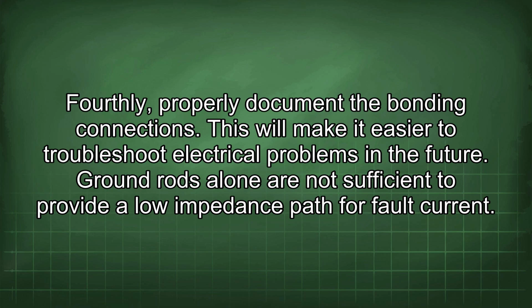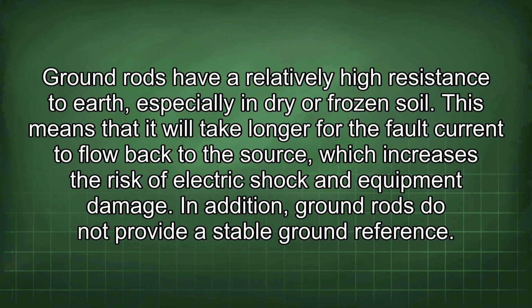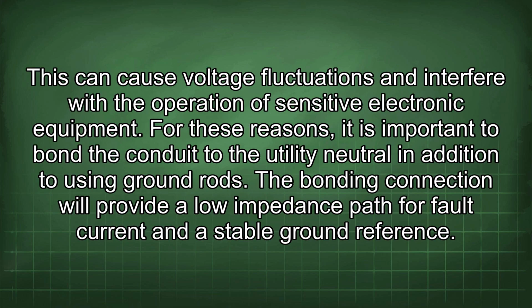Ground rods alone are not sufficient to provide a low impedance path for fault current. Ground rods have a relatively high resistance to earth, especially in dry or frozen soil. This means that it will take longer for the fault current to flow back to the source, which increases the risk of electric shock and equipment damage. In addition, ground rods do not provide a stable ground reference. This can cause voltage fluctuations and interfere with the operation of sensitive electronic equipment. For these reasons, it is important to bond the conduit to the utility neutral in addition to using ground rods. The bonding connection will provide a low impedance path for fault current and a stable ground reference.